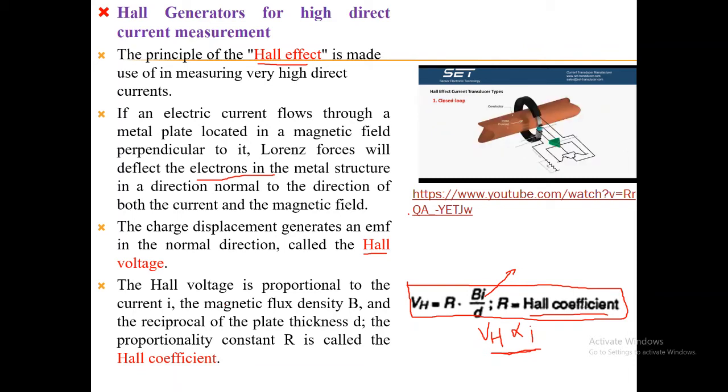The second type is closed loop Hall effect current transducer. The closed loop Hall current transducer introduced magnetic field balance into open loop Hall effect current transducer. When primary current goes through the conductor, it generates magnetic field around the conductor, then put the conductor through the center of a ferromagnetic core to concentrate the magnetic field, and place a Hall element in the gap of the core, then we will get the Hall voltage. After the Hall voltage is transmitted to the amplifier, the amplified current signal is sent to the secondary coil. The magnetic field generated by the secondary coil is opposite to the magnetic field generated by the primary current.